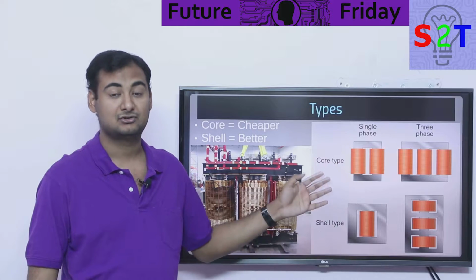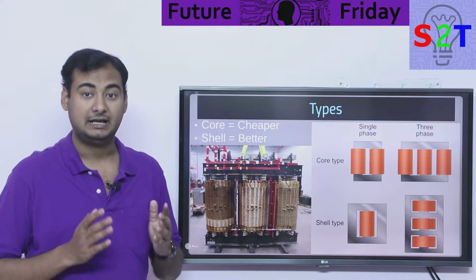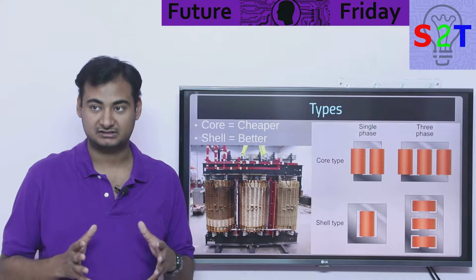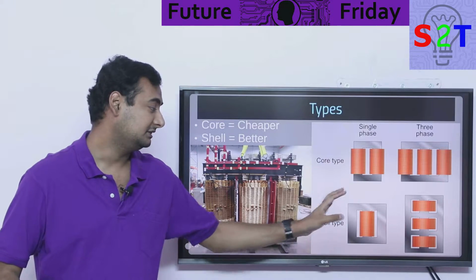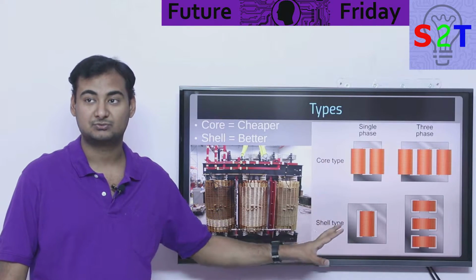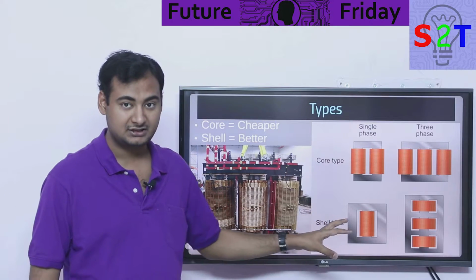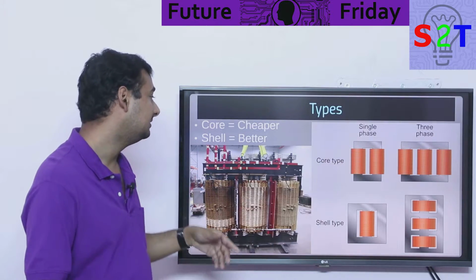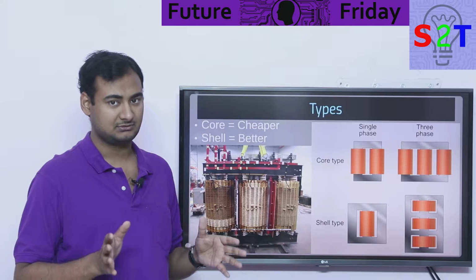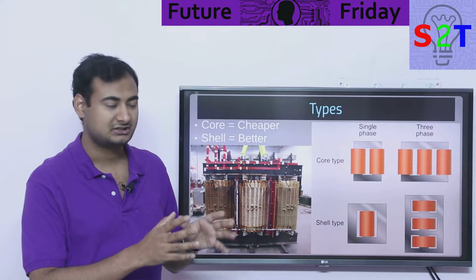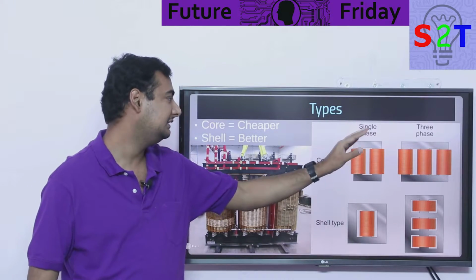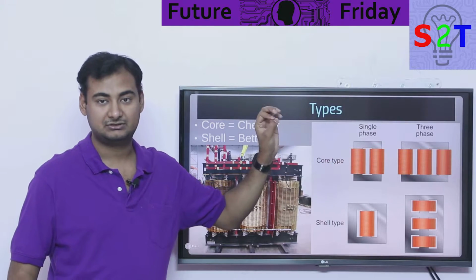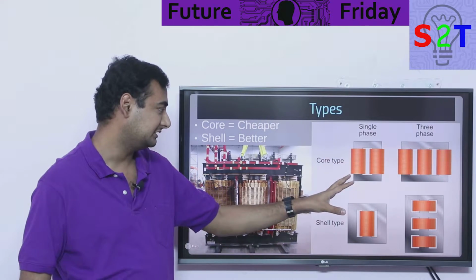Now there is shell type. Shell types are actually more efficient, and they are also what we call more short circuit resilient - if there is a spike current, these can handle it and dissipate it much more effectively. So these are better transformers, however this is cheaper. This is why almost all transformers you'll see in pole mounted substations or things of that nature would generally be core type - basically it has the bare minimum it needs to have.